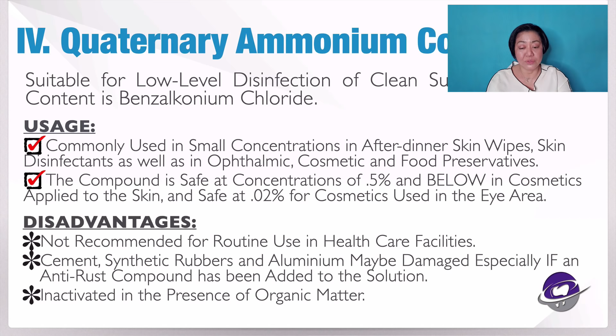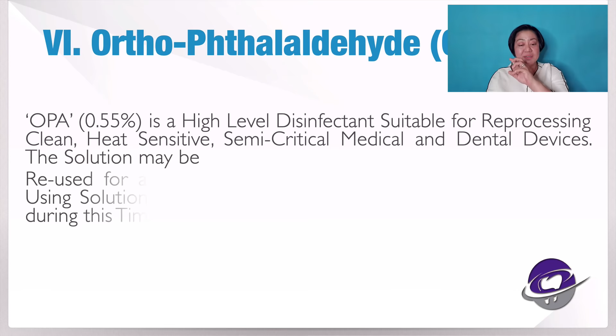Another is the quaternary amine solution. This is quaternary ammonium compounds with a low concentration of alcohol. So this one has a low alcohol-base effect, and this is also seen in certain wipes that will tell you alcohol base. Okay, so next is OPA. Now I will not pronounce what the P stands for, because it's very hard to pronounce. But this is a high-level disinfectant suitable for reprocessing clean, heat-sensitive, semi-critical medical and dental devices. It can be reused for a maximum of 14 days and should be monitored using solution test strips.